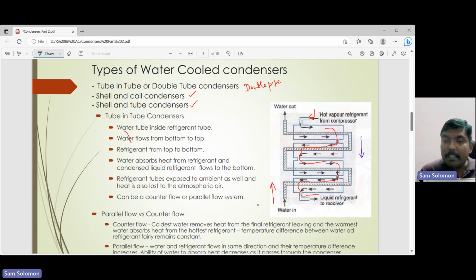Whereas the water that is entering in is going to be cold water. This vapor loses heat as it comes down, and so it is going to have less heat. So that lesser amount of heat is easily removed by this water. And then as it goes up, it further takes heat from a relatively higher temperature refrigerant. Here the temperature is higher, here the temperature of water is lower. So the temperature difference between the water and the refrigerant is maintained in every single step.